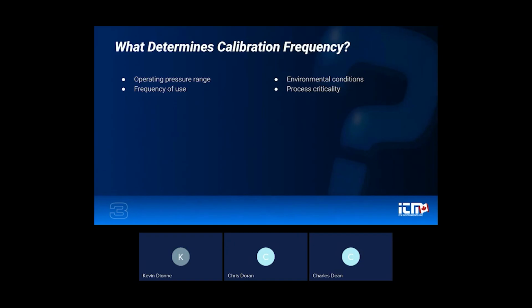Temperature swings, vibration, moisture, or harsh process conditions can all accelerate the drift. And finally, process criticality. If a pressure reading is directly impacting the safety of you as a technician or your technicians, that's something you're going to take more seriously than if it's not, because simply the risk is higher. So it really depends on your application, and it depends on external factors. The 6 to 12 months that you hear is really just a rule of thumb, for lack of a better term.